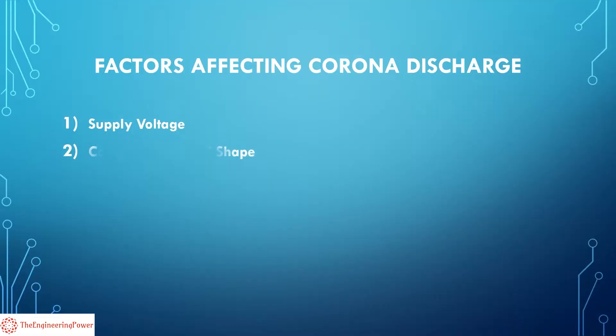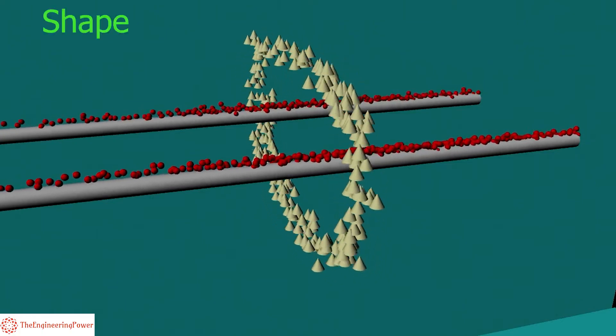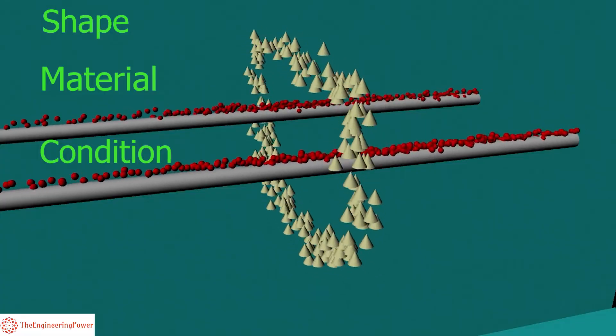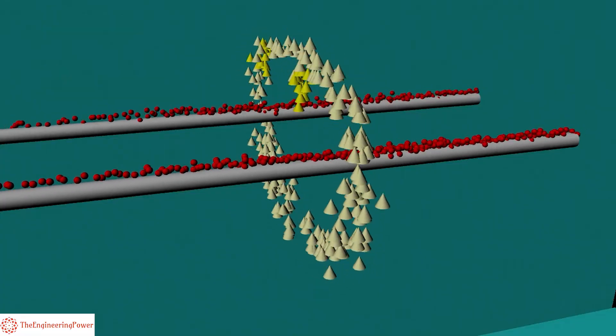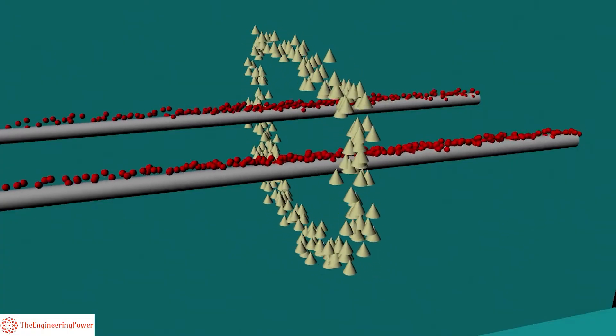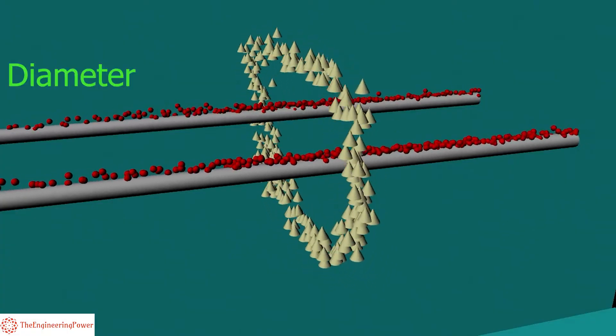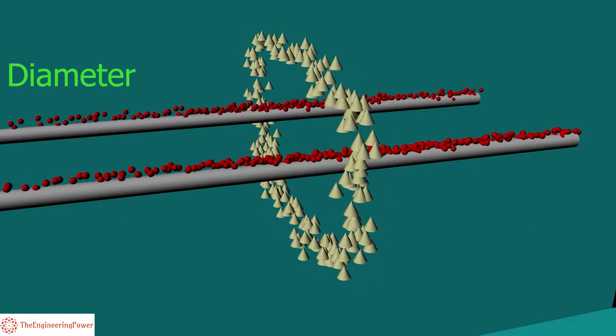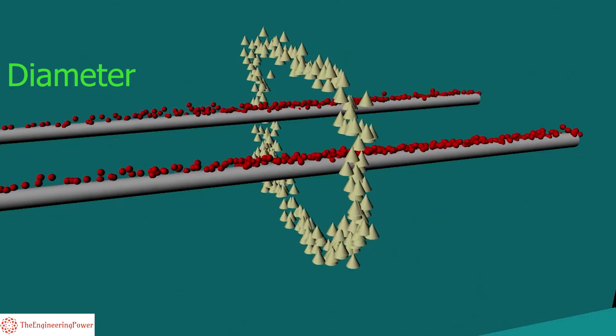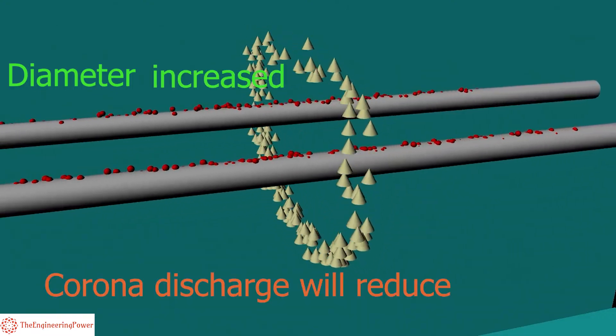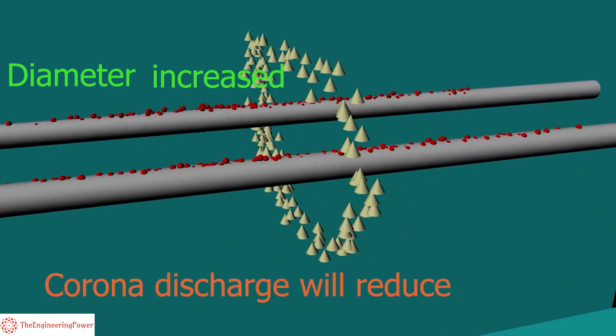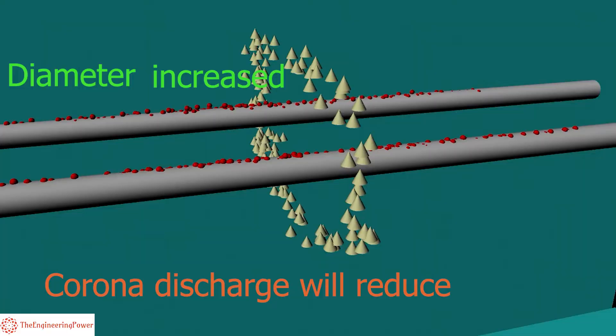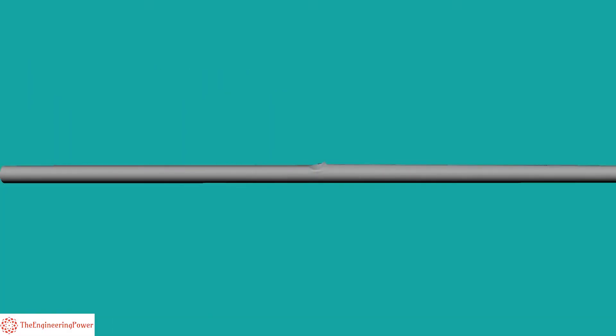The second factor is the conductor shape and surface. Corona effect also depends upon the shape, material, and condition of the conductor. Corona discharge has an inverse proportionality relationship with the diameter of the conductor — if the diameter of the conductor is increased, the corona discharge will reduce considerably, and vice versa.